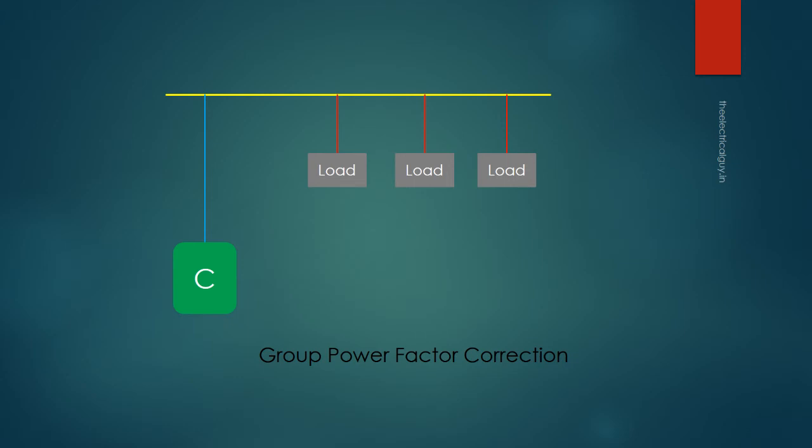So for example, if you have three similar induction motors which are being used for the same reason, you can use a common capacitor bank for power factor correction. This method is also economical but recommended only for small loads.